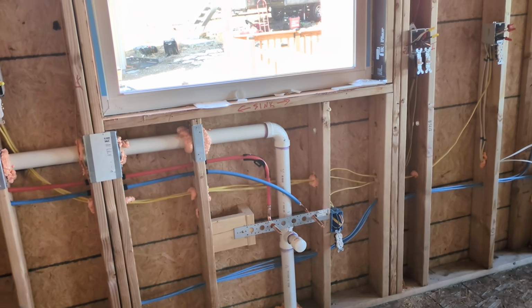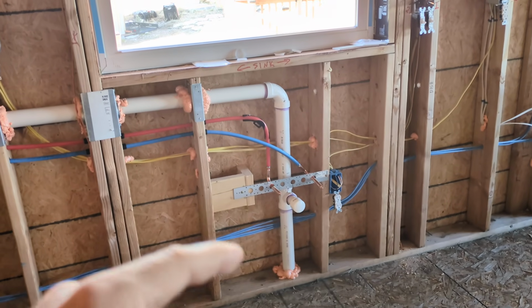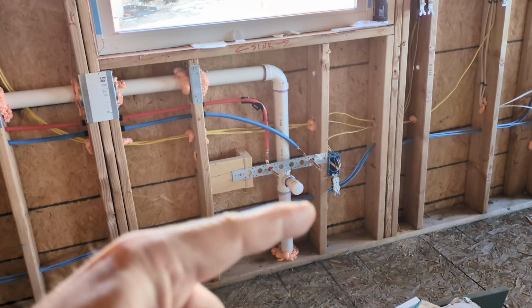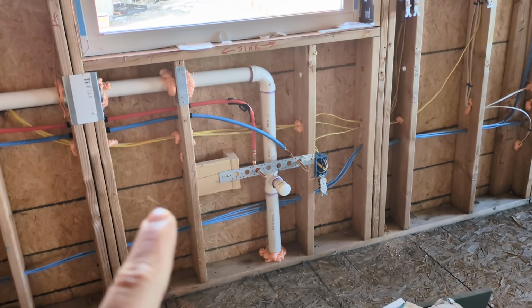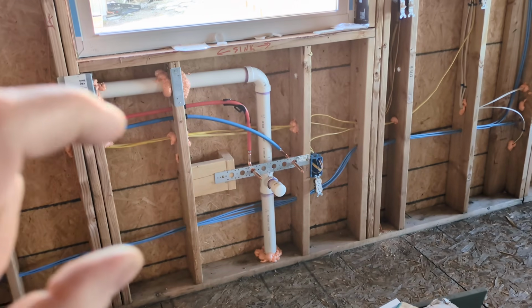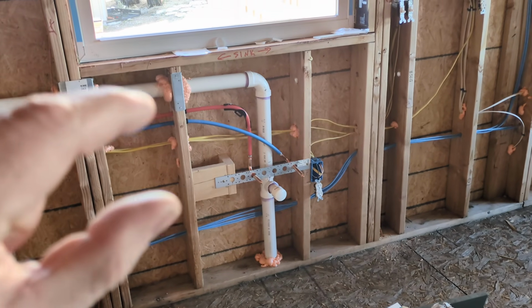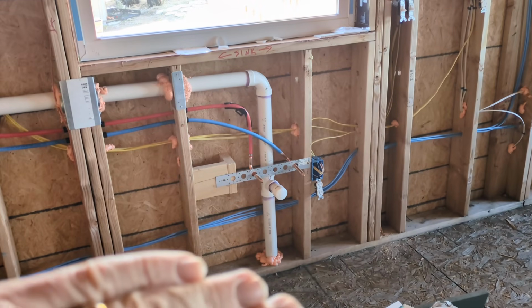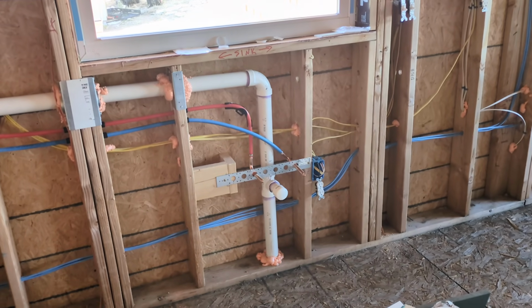But basically what happens here is I've got my drain pipe coming down, my stub coming out for the sink, and then there's going to be a trap, right? And then the bottom of the sink is going to be about here, but that's not what they care about any longer. What the code is now requiring is that if that sink was full of water, absolutely full to the brim and overflowing onto the counter, when you fix that clog, they want the water to go down, right?